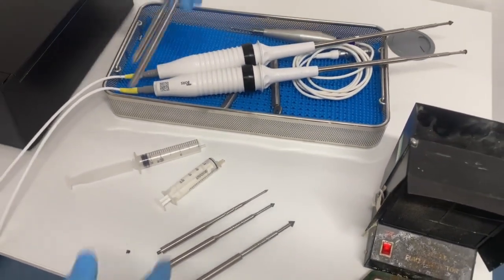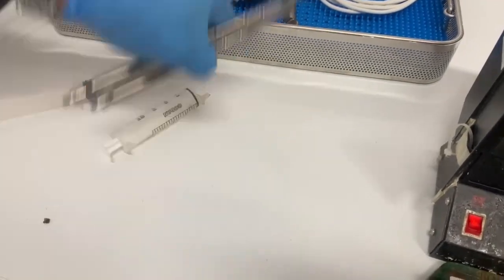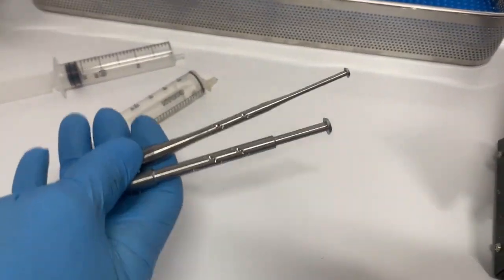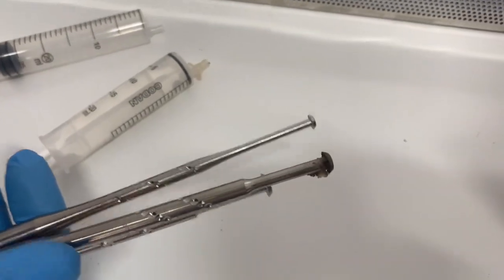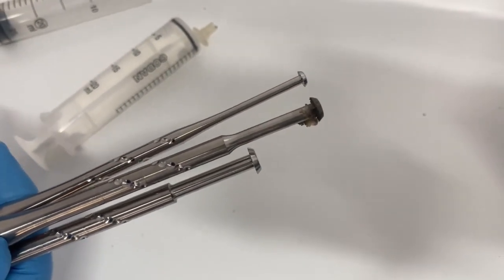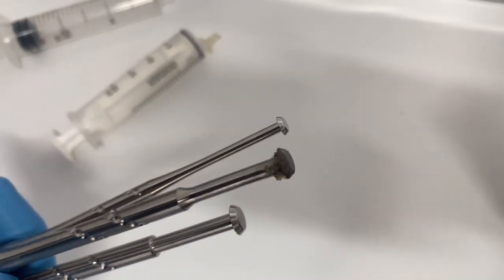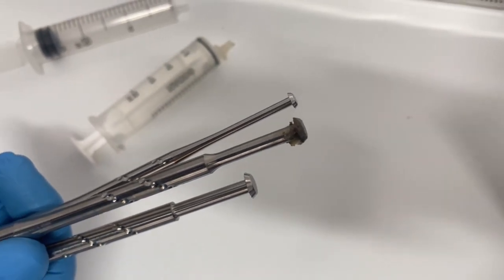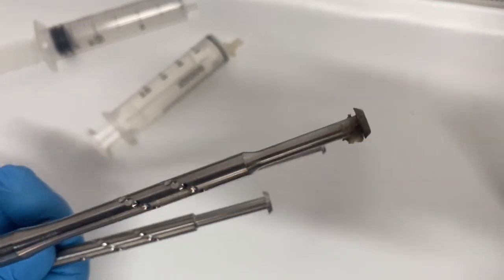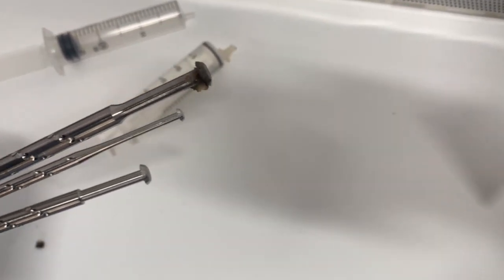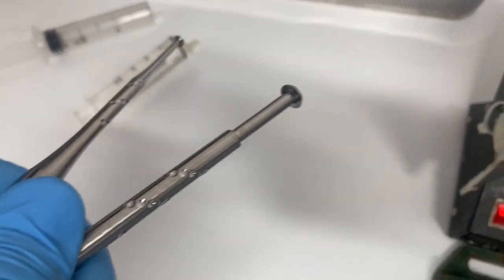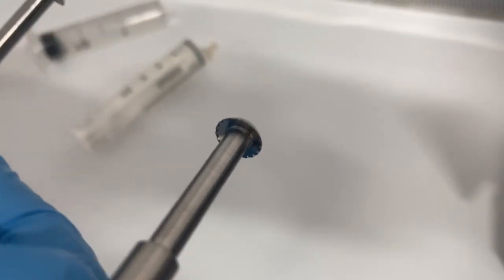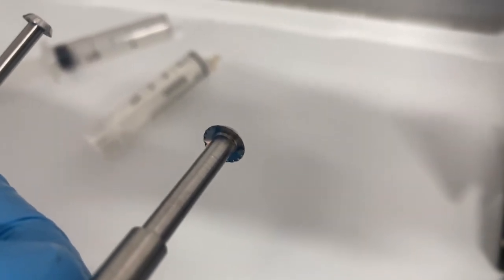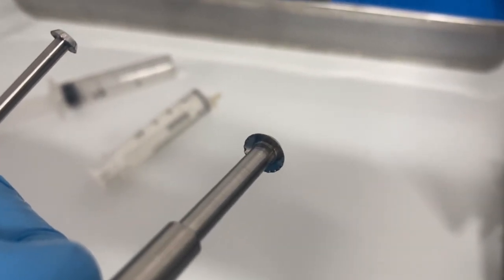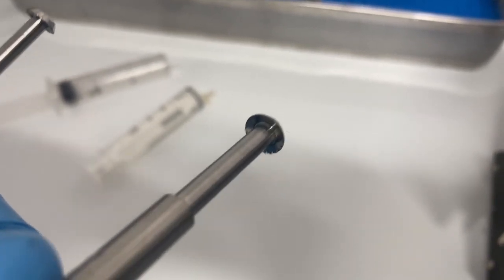And looking at the scrapers, there are 3 sizes of scraper: 6 mil, 8 mil and 10 mil. And these are quite unlike conventional systems. They're flat fronted because they are just going in and scraping back. And also they have these little torsional serrations on the underside flange. That is using the torsional element of the vibration to help deliver the energy more efficiently.